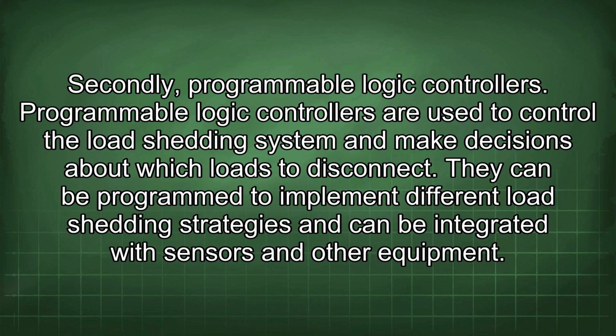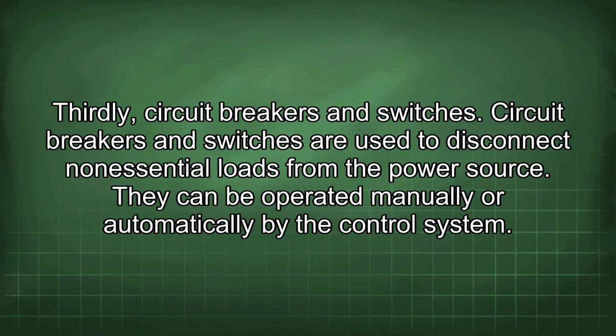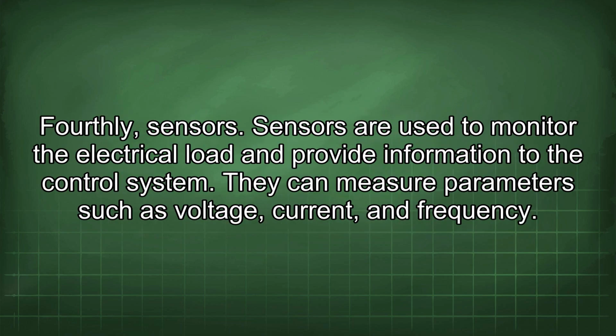Secondly, programmable logic controllers. Programmable logic controllers are used to control the load shedding system and make decisions about which loads to disconnect. They can be programmed to implement different load shedding strategies and can be integrated with sensors and other equipment. Thirdly, circuit breakers and switches. Circuit breakers and switches are used to disconnect non-essential loads from the power source. They can be operated manually or automatically by the control system. Fourthly, sensors. Sensors are used to monitor the electrical load and provide information to the control system. They can measure parameters such as voltage, current, and frequency.